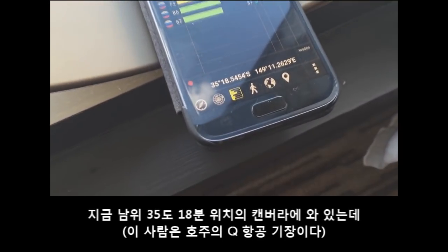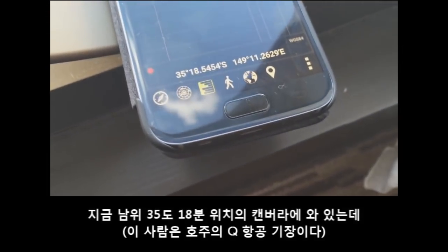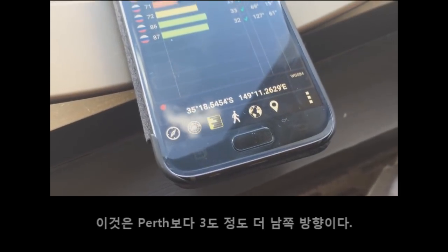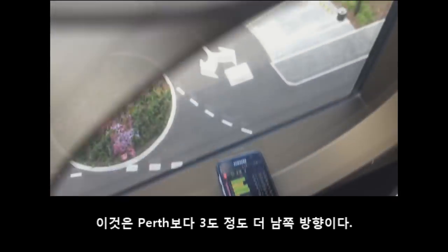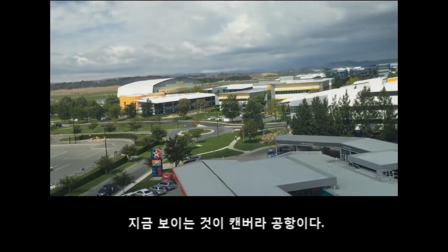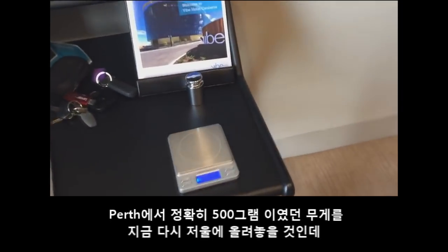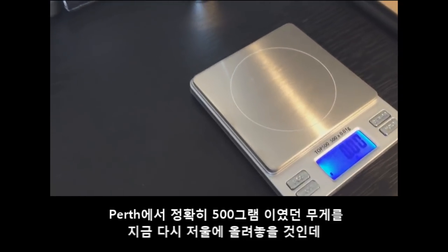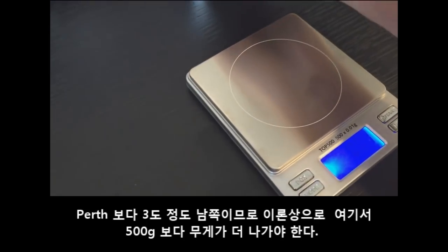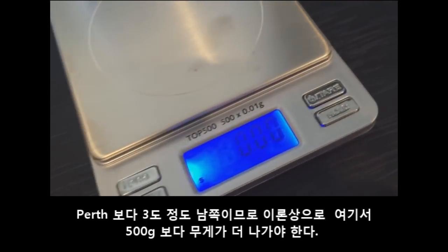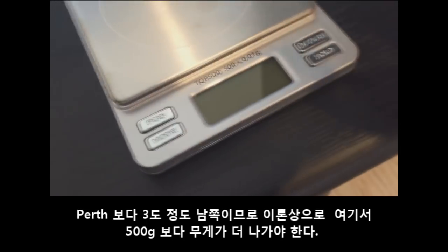So I'm now in Canberra, Australia, which is a latitude of 35 degrees 18 minutes south. So it's more than 3 degrees further south than Perth was, and that's just looking out over Canberra Airport.